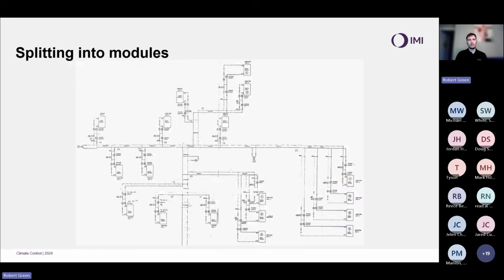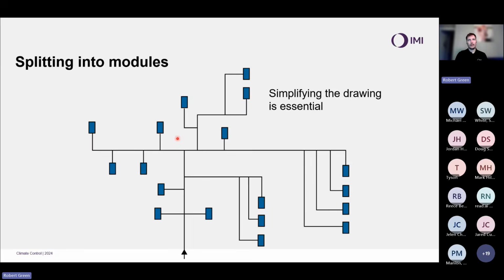I want to simplify this drawing. Really important thing, first thing to do is simplify that drawing. Take out any strange things of how it's drawn and just do it really simply. Because we're running a direct return system, we can represent the flow and return pipe for this exercise as a single pipe. So this pipe is representing the flow and return, serving each of these units. Simplified my drawing, making it nice and easy.